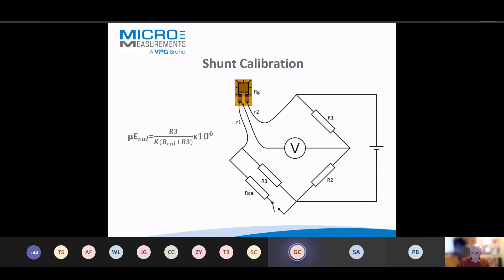R2 would cause the same desensitization to the strain gauge, so when I throw this switch, if this doesn't read 1000 microstrain here, I can boost the gain to read 1000 and automatically compensate for the lead wire resistance. That's really good if you're working on something like a bridge, where you might have 50 or 100 meter leads. The shunt cal circuit lets you automatically correct for that lead wire desensitization, and in digital instrumentation, you press a button and it does the calculation for you.